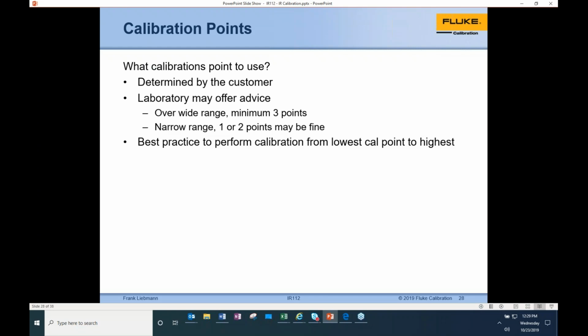Kind of driving into calibration points. This is a little bit of a subjective matter, so it can be determined by the customer. If you're doing it, say, on a shop floor, and you have a very specific process and you don't need to check the optics across the full range, you may do a limited range. So you could have differences in a wide to small range. You may only be checking 1 to 2 points. Calibration points and getting into the procedural piece of it, it's all about how you define the scope of what you're looking to do and what you're going to do to stay in compliance to that scope.